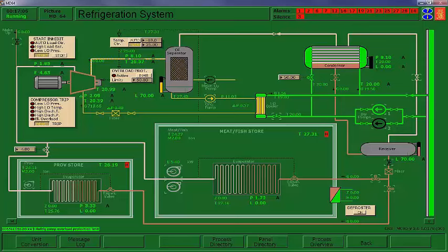So right now we've got about 1.7 bar suction pressure and 8 bar discharge pressure. And again, that high pressure coming into the condenser is raising its saturation temperature above the salt water temperature so we can condense it. All right, we're down to 1 bar. I'm going to go ahead and put the liquid on and put the control in automatic, and it should run itself. Now we will probably get an alarm on this provisional store box, which is fine.